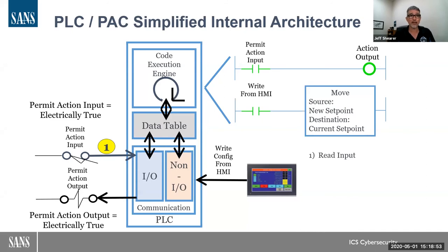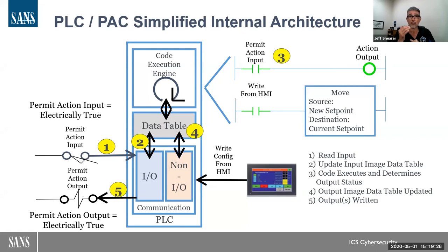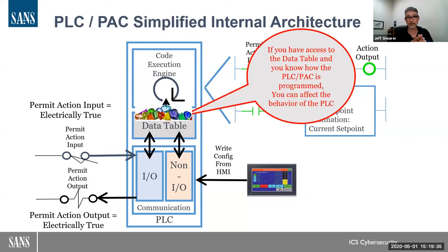In normal operation: first we read the inputs, then we update the data table with a current snapshot of all inputs — analog or digital. Third, we solve the ladder logic or structured text or function block logic. Fourth, we put those new values back into the data table. Fifth, we update the I/O image table and write those new output values or hold the last output values to the actual physical devices. What we don't often think about is what would happen if we just write to the data table and let the architecture update the logic or I/O table based on false values.